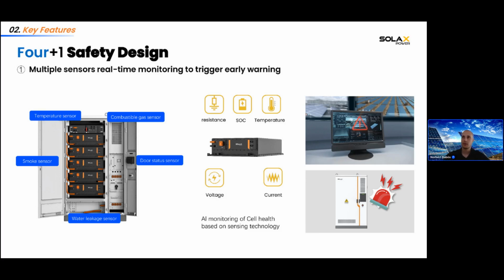About the safety features of both the TRENE and AELIO, it's called the 4+1 safety, because as you can see in the picture, there are many sensors inside the battery cabinet, which monitor all kinds of data in real time. If something goes wrong inside the cabinet, the first level is that the sensors measure some abnormal values, like resistance, temperature rising, voltage or current mismatches. Then it will give you an alarm on the monitoring site, or send you an email or an SMS that you have some kind of problem with the battery.